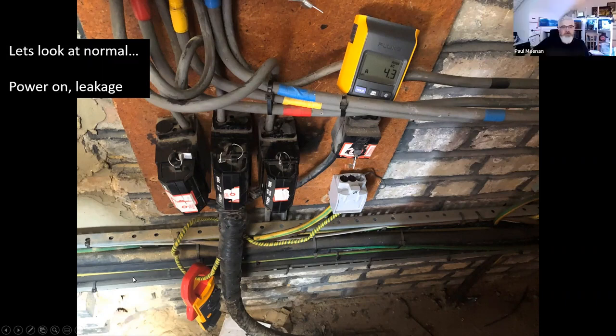We call this protective conductor current - some people call it installation leakage. There are different methods and means of measuring it. There's a great document available online that shows where and how to put your clamp meter to measure installation leakage between your line and neutral tails, and also your protective conductor current on your earthing. But that's normal, perfectly normal.